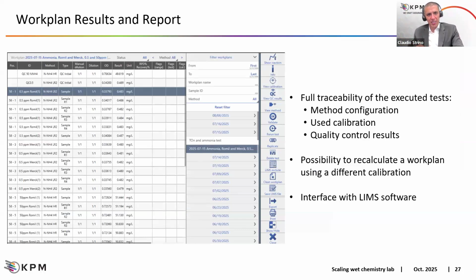We also have a really versatile result page and report feature. Really important for accreditation purposes, we have not only a full audit trail concerning what has been done by each operator, but we can also see and recall info concerning method configuration when selecting a specific result. This is the full list of features available for us. And we can see we have method configuration. By selecting view method, we can review all method settings used to obtain this result, to run this test. By selecting view calibration, we can see what calibration has been used to obtain the selected test, the selected result.